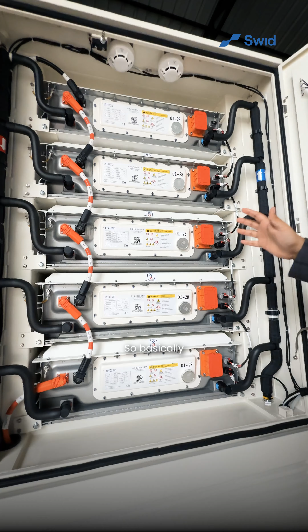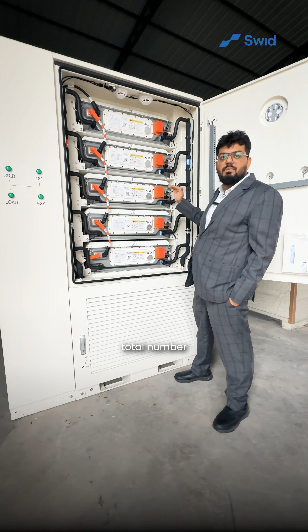Each battery pack consists of 3.2 volt, 314 ampere hour, 52 cells in series. These 5 packs are also in series, making the total number 260 cells of 3.2 volt, 314 ampere hour. So the total calculation comes to 261 kilowatt hour.